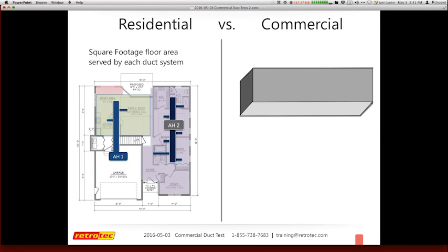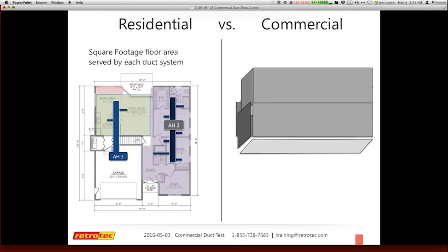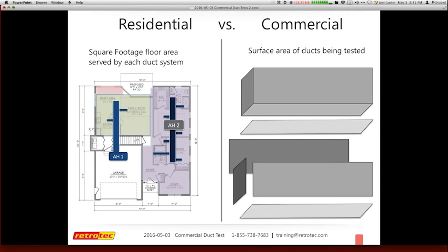and I do have some references for the code references or the ASHRAE standards. So these are actually in the standards for ICC on how they refer to use the SMACNA method if it's above 3 inches or more. So SMACNA is just the standard, or the accepted applied way of performing the test. There are others out there, but I don't think there's anything as diverse or as popular, I guess is really the word, on how to apply a testing standard.